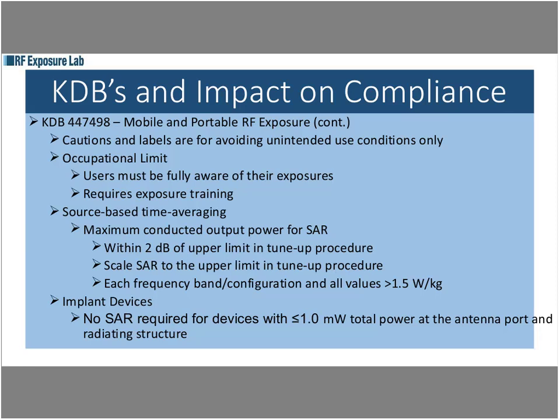They added more measurements in the test requirements about 2 years ago, and that's just a requirement that they now have. For implant devices, if your device transmits either radiated or conducted power less than or equal to 1.0 milliwatts at the antenna port or the radiating structure, then there is no SAR requirement. You can be excluded from actually having to do a SAR measurement, or in this case, an FDTD evaluation. Nothing is required. All you have to show as proof is that your device cannot exceed 1 milliwatt in power.